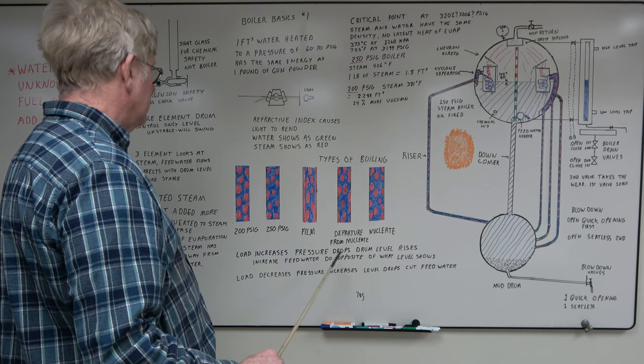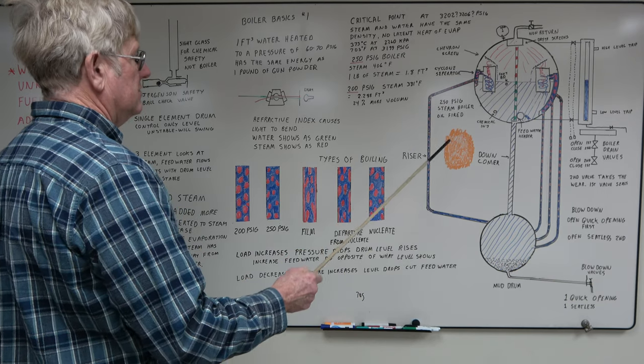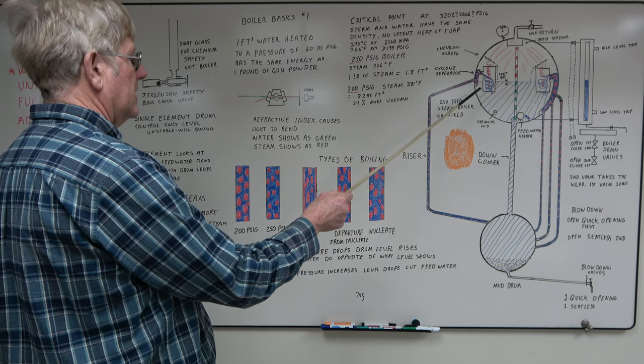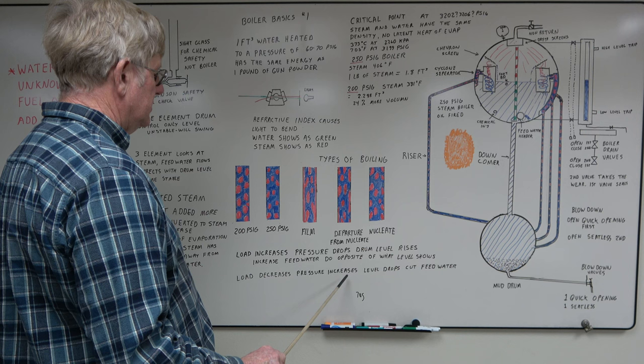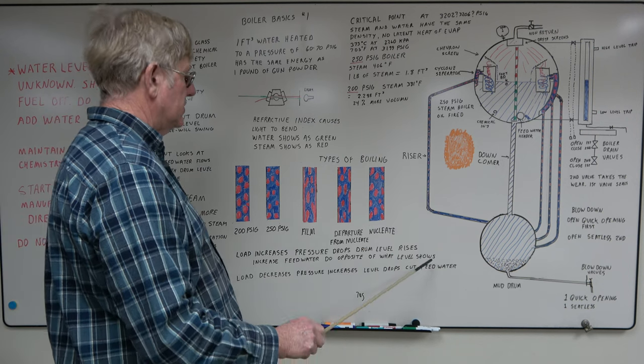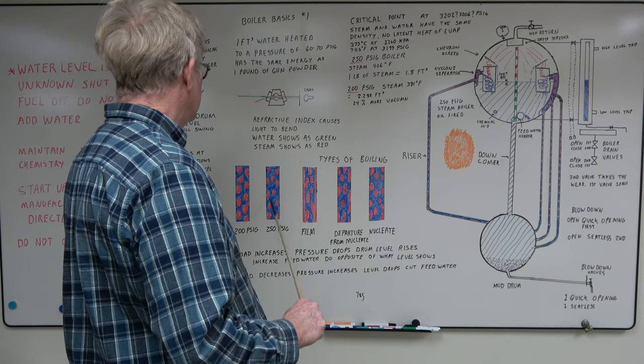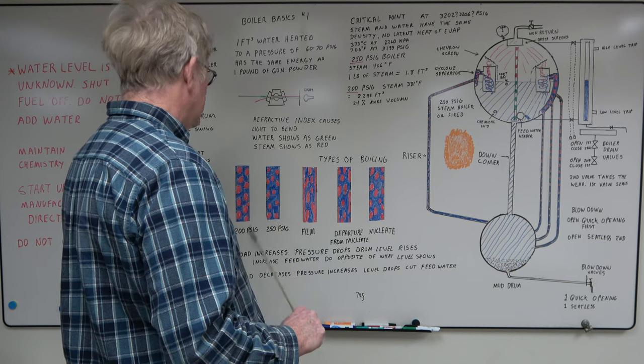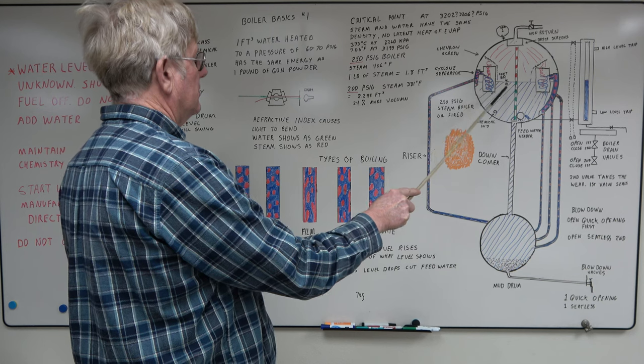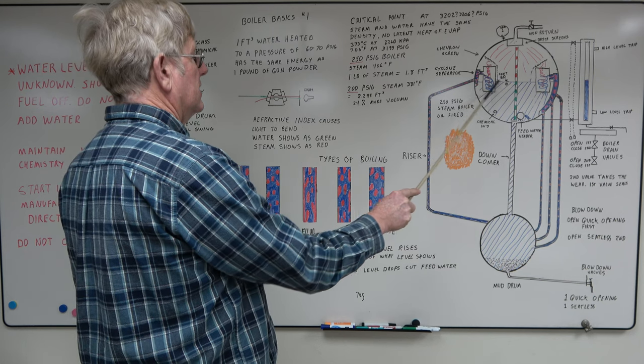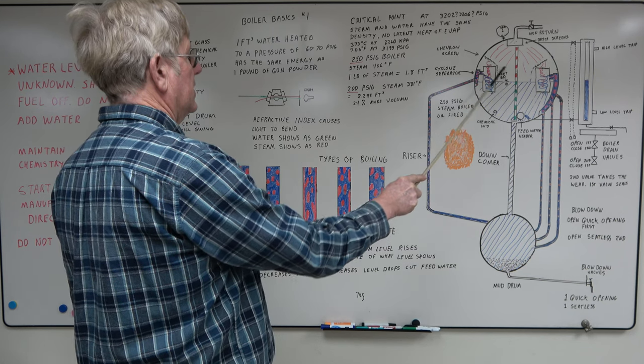The opposite occurs if you drop load. Let's say somebody shuts a valve, loses a piece of equipment. Steam flow drops, your pressure comes up. Load decreases, the pressure increases and the level drops. Your steam bubbles become smaller, they get squeezed. At this point, your drum level is going to drop. Your feed water valve is going to try to open or you're going to try to put more water in and we get back to normal. Now the pressure comes back, now it's going to be high.